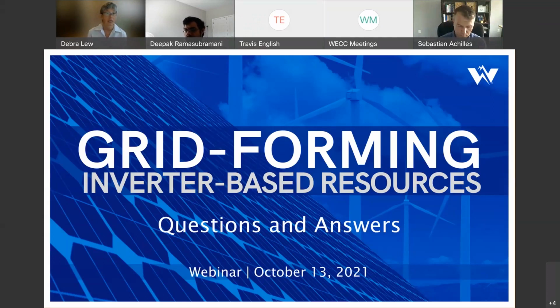The question was about WSCR, when coming up with that value, whether evaluation included N-0 or N-1. We tested different types of contingencies, N-1, but the WSCR value of 1.5 is a metric determined based on more detailed PSCAD studies, and the metric itself is pre-disturbance, because we need the calculation to be very fast in real time. There's no time to recalculate for different contingencies. So in real time, it takes a short circuit calculation based on actual topology at the time, and actual production from inverter-based resources in that area. As long as it's 1.5 or higher, there's no limitation on inverter-based resources. So that 1.5 value is pre-disturbance, but determined based on simulating different contingencies in planning studies.